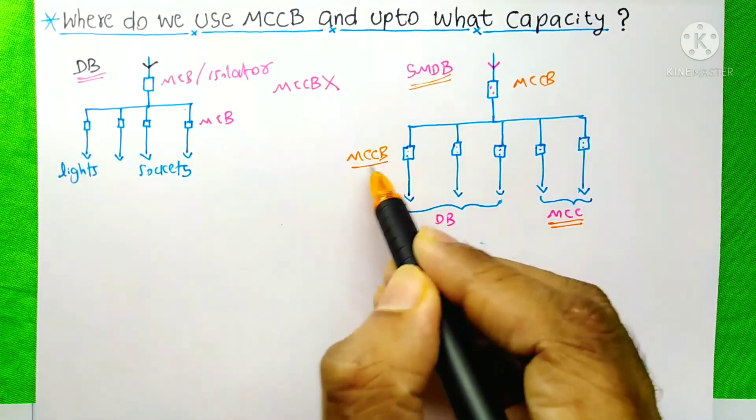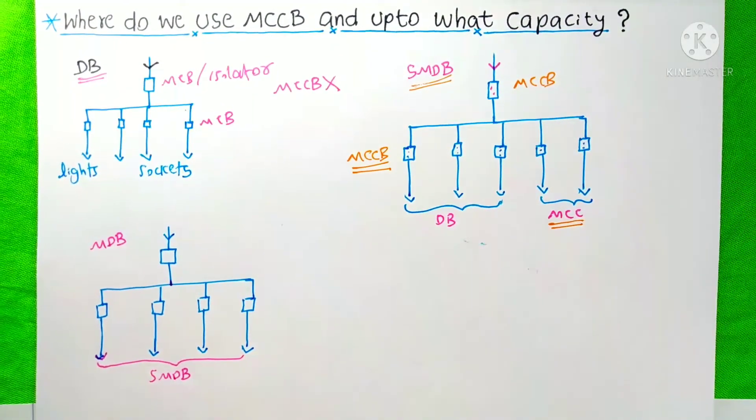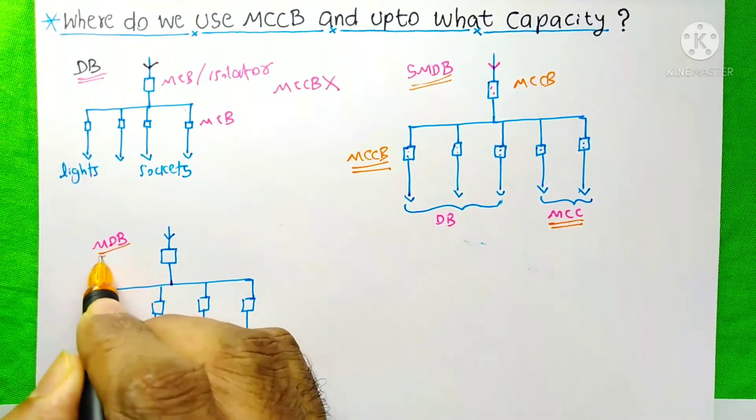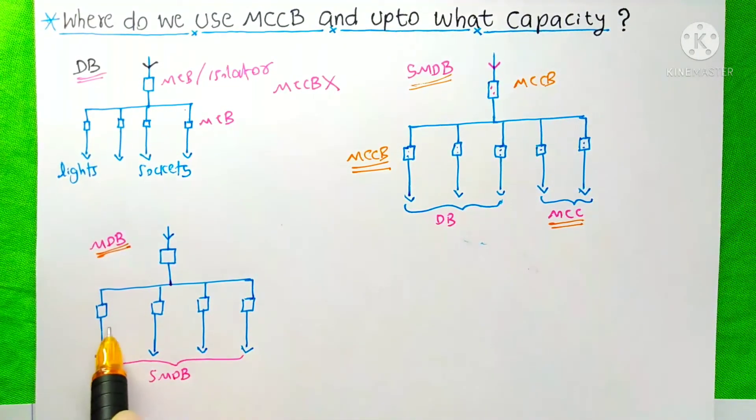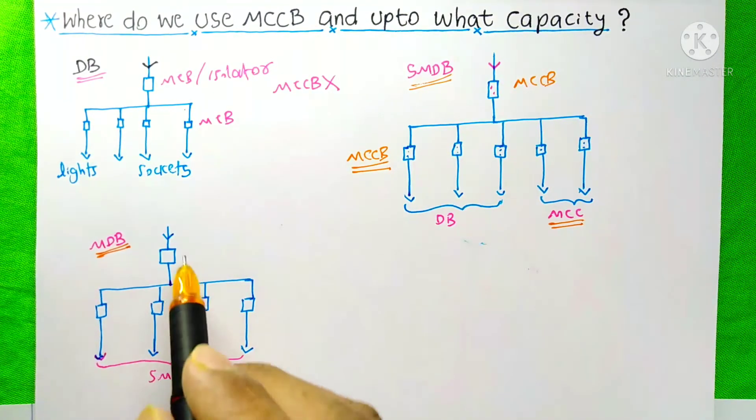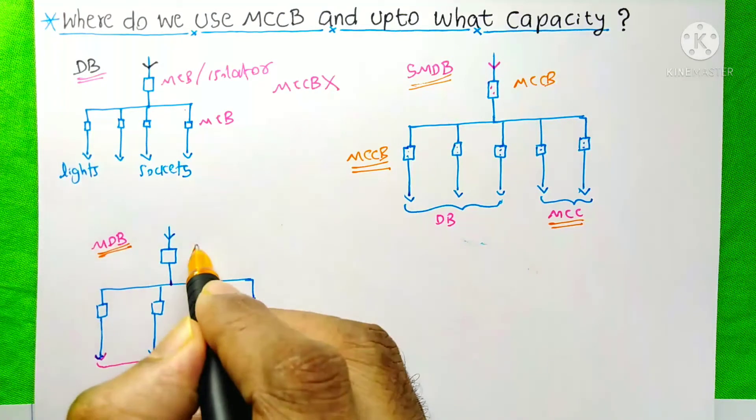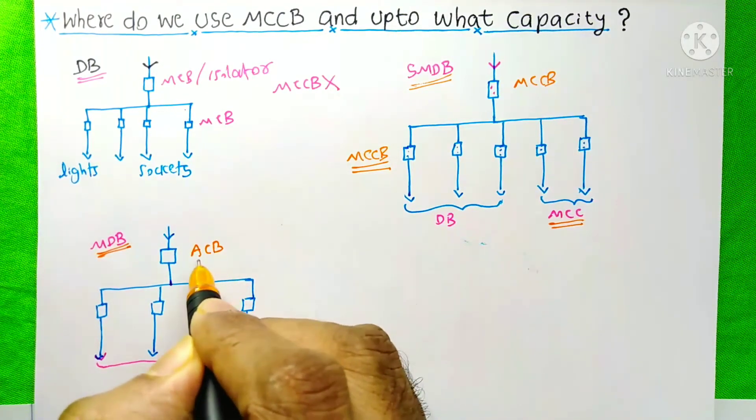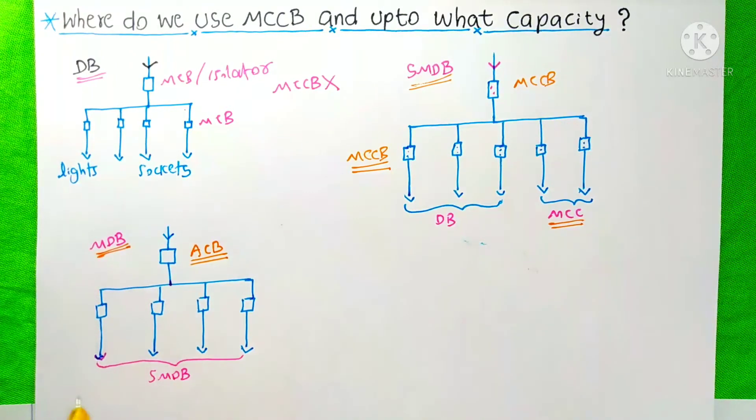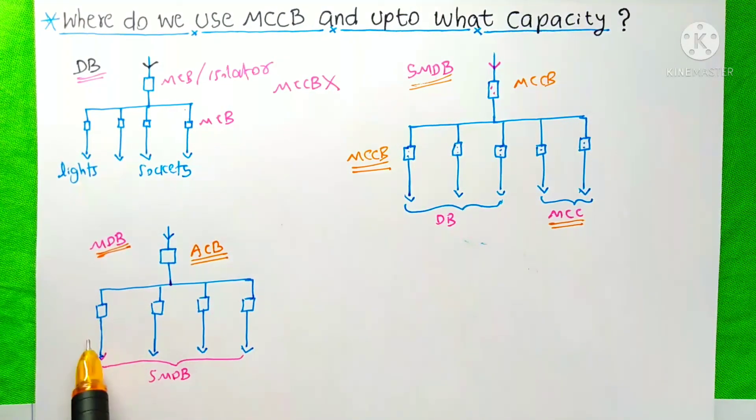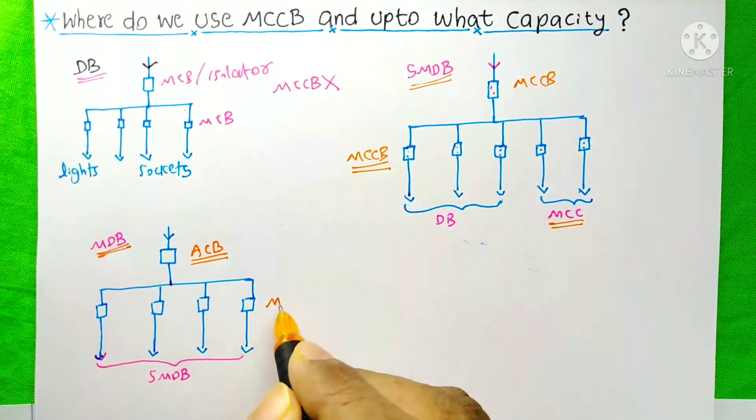The next case is about the MDB, main distribution board. It is the main breaker and these are the branch breakers for this MDB. Generally we use ACB, air circuit breaker for the Incomer of this MDB. And for the branch breakers, we generally use MCCB.